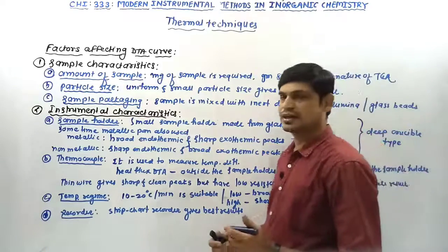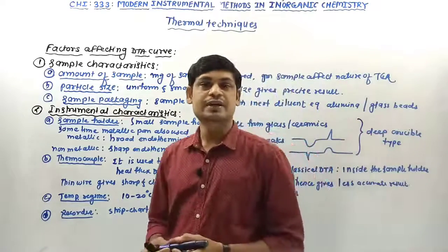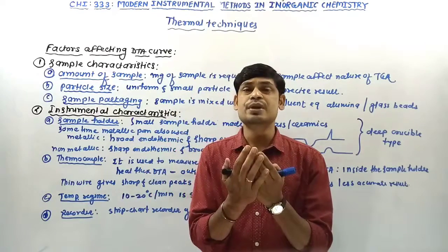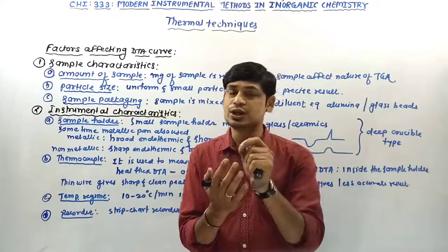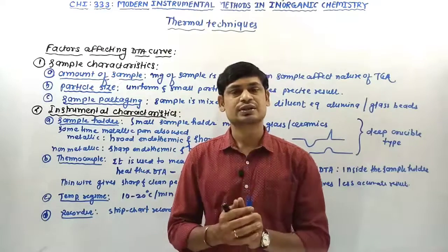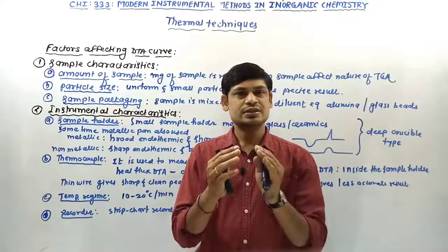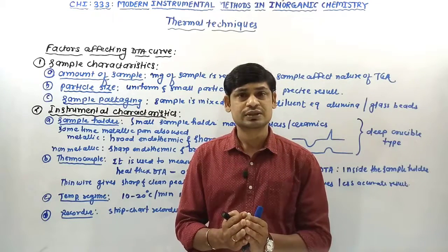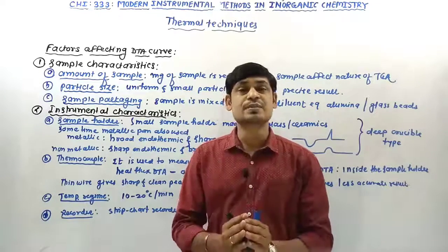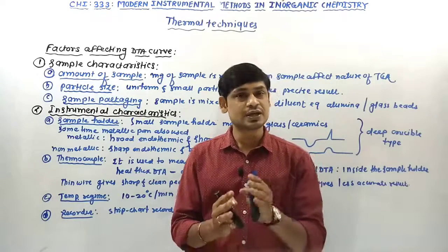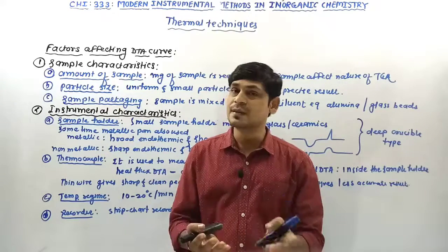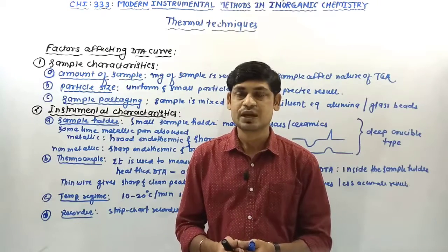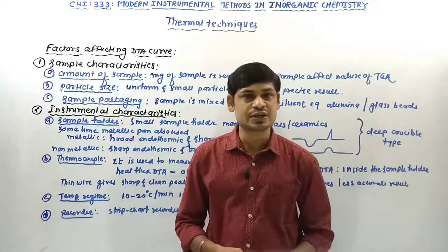Now the environmental characteristics, environmental factors. The environment inside the sample holder also affects the nature of the DTA, because the gaseous atmosphere present in the sample holder can react with the reactant or product, that is the sample, or you can say the reference also. Unwanted peaks may be obtained due to that reaction.